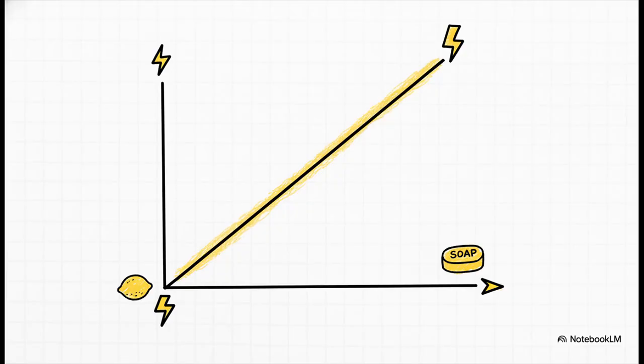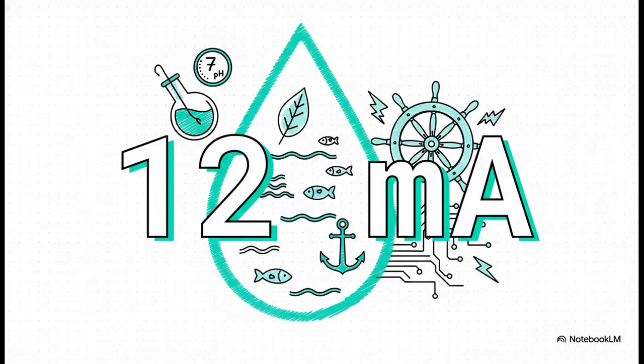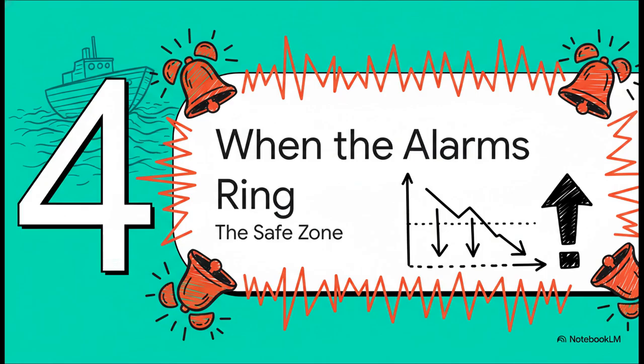So the most important thing to get is that this relationship is perfectly linear. It's a simple, direct scale. As the water's pH goes up and gets more alkaline, the milliamp signal from the transmitter goes up right along with it. It's elegant, and honestly, it's beautifully simple. And that brings us to the magic number, 12 milliamps. When an engineer sees 12 milliamps on their monitor, they know the water has a pH of 7. It's perfectly neutral, not acidic, not alkaline. That is the number everyone wants to see. But things don't always stay perfect, right? So what happens when those numbers start to drift?